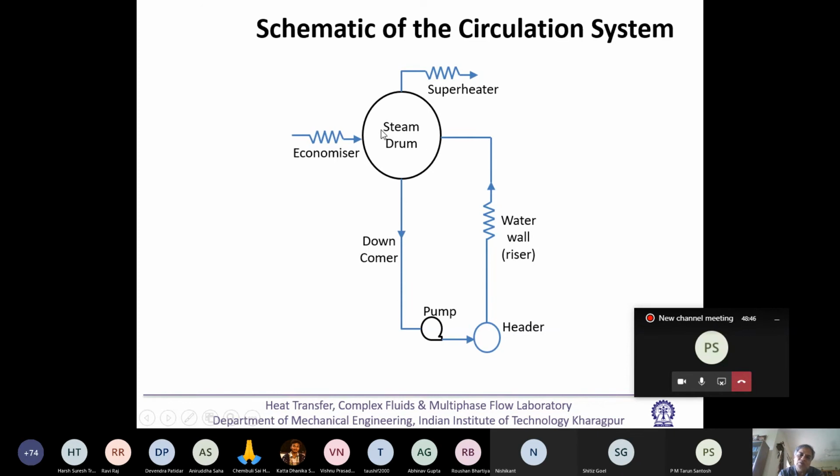This water is almost at saturation temperature, so steam will not condense, but will get separated out of this pool. Only a very little bit of moisture will remain, and it will not be superheated. It is almost saturated steam with some moisture, and that goes out of the steam drum. We have to take it to the superheater.